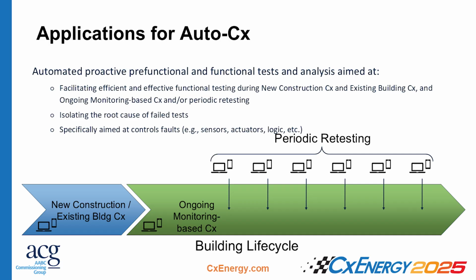traditionally right now is only done at certain points within a project, right? Whether it's new construction, at the end of new construction, we're about to hand that project over to a building owner, or if you have some sort of renovation happening, you do some commissioning there. Or you may have ongoing commissioning, monitoring-based commissioning. We're thinking that functional testing can be done throughout the life cycle of a building, right? This is something that has value at the beginning where you're about to hand this over to an owner, or in the aspect of periodic retesting, right? So be able to do this over the span of the building's life, every month, every quarter, to ensure that you already have the infrastructure in place, you have the points being brought into certain software, so you could just redo this over and over again.